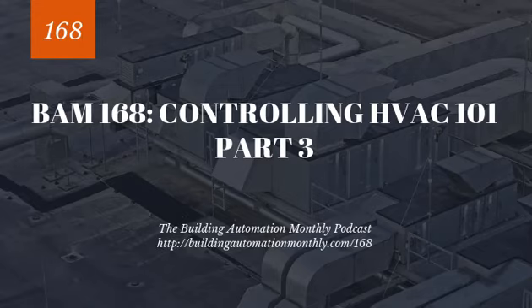But there is a real simple calculation in order to calculate tonnage. For those of you who are interested, here it goes. First you have to calculate your temperature differential, right? So you're going to calculate the incoming water temperature and the required chilled water leaving temperature, so the entering temperature and the leaving temperature at full load. Then you're going to look at your gallons per hour times 8.33 times that delta T we just calculated. That's going to give us our BTUs per hour.